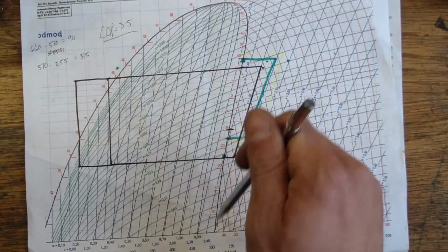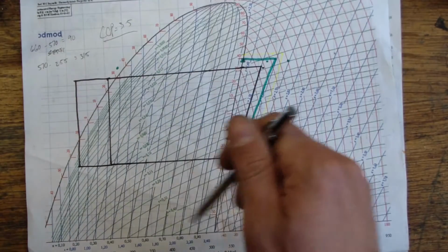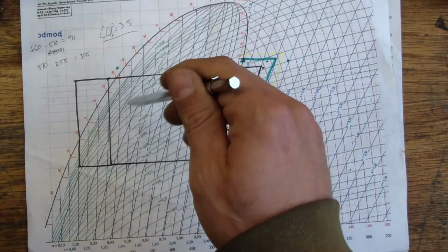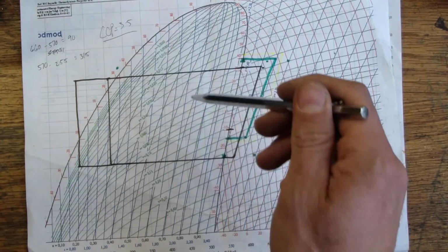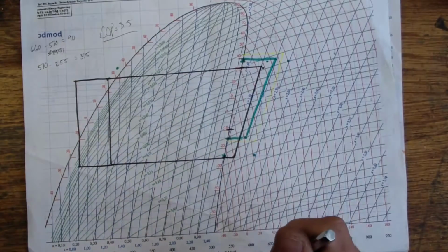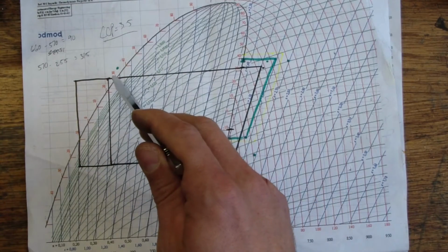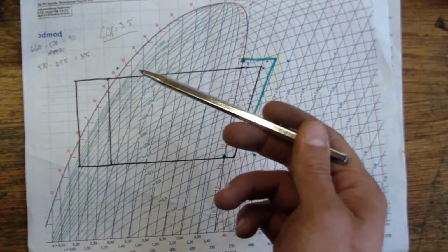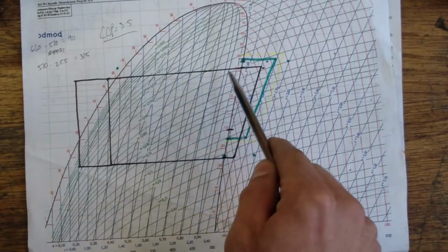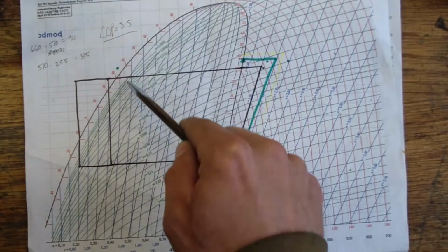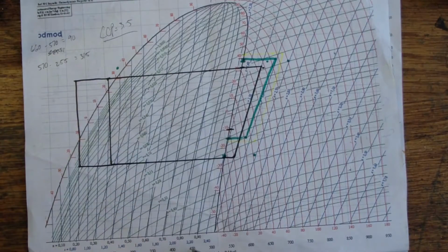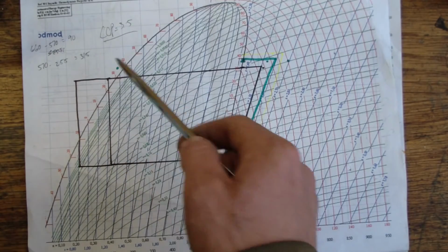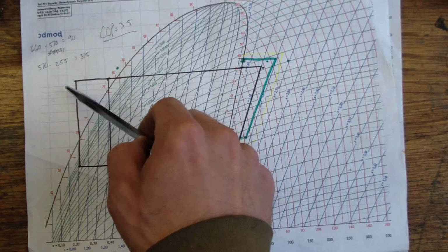We've discharged a lot of heat to the environment. We've lowered the pound or kilogram of a certain amount of enthalpy, and we've condensed that vapor into a liquid state. Now, if we continue to cool that liquid beyond the saturated liquid curve, we call that subcooling. Because once we get over here, these isothermals are no longer horizontal, they actually start to travel vertically. So as we continue to cool it, we remove enthalpy, we're in a liquid state, we start to reduce in temperature. And the more heat we discharge, the lower the temperature.